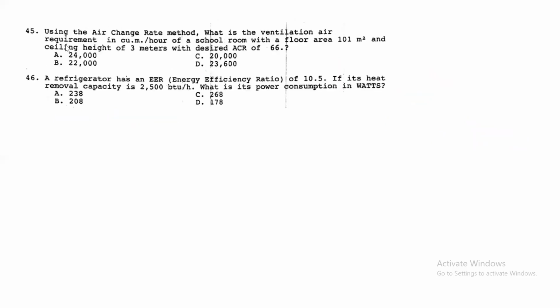So next, 45. Using air change rate method, what is the ventilation air requirement in cubic meters per hour of a schoolroom with a floor area of 101 meters squared and ceiling height of 3 meters with desired ACR of 66? So paano to, guys? So, ano lang din to, no? Unit analysis na lang din. So, itong 45. So, 101 meters squared multiplied by 3 meters, so times 66.